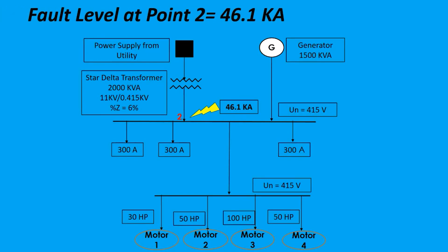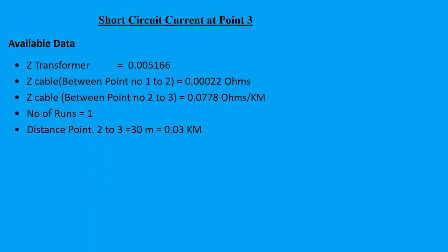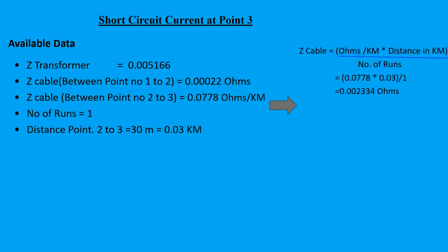Next, we'll see the short circuit current at point number three. Available data: Z transformer is 0.005166 ohms, Z cable between points one and two is 0.00022 ohms, and Z cable between points two and three is 0.0778 ohms per kilometre. The number of runs is one and the distance between point two and point three is 30 metres, which is 0.03 kilometres. Z cable equals 0.0778 multiplied by 0.03, all divided by one, which comes to 0.002334 ohms.